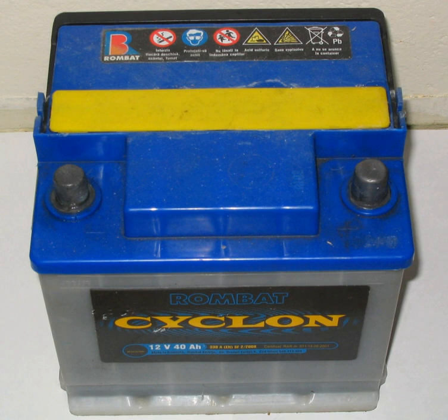IUoU battery charging is a three-stage charging procedure for lead-acid batteries. A lead-acid battery's nominal voltage is two volts for each cell. For a single cell, the voltage can range from 1.8 volts loaded at full discharge to 2.10 volts in an open circuit at full charge.